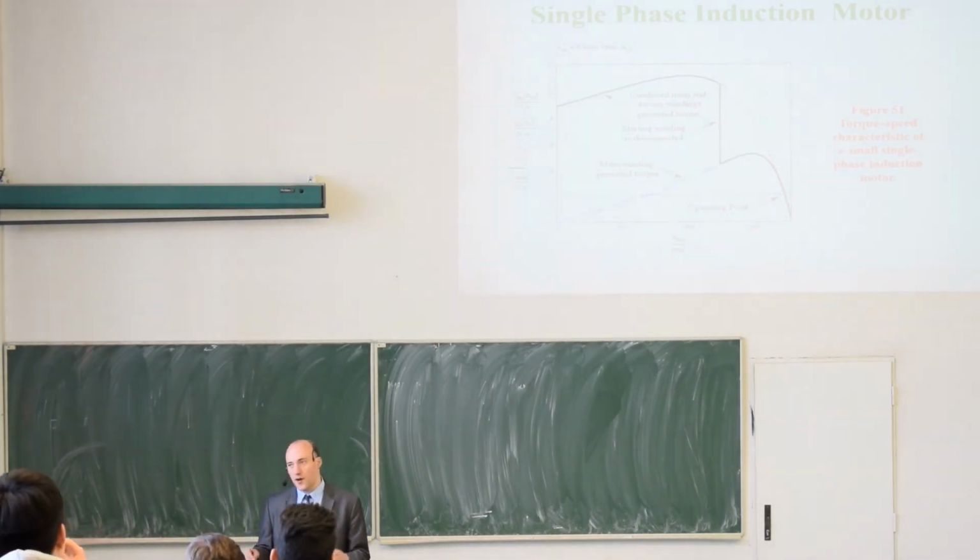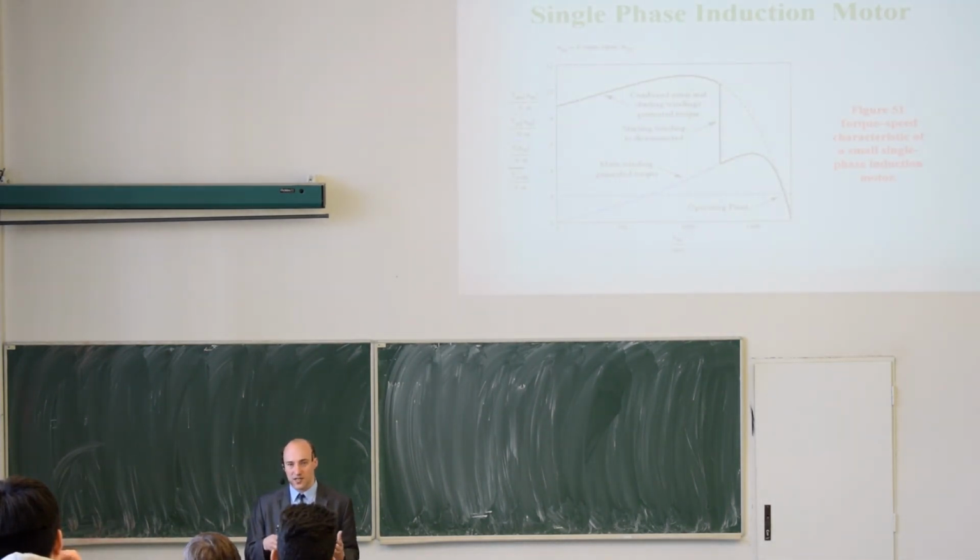So single-phase motors are not used for large applications. You will not find single-phase induction motors for 100 kilowatts, for example, because for this kind of power, the current going through the line would be very big. And since in the three-phase network, the current is much smaller, larger appliances are using three-phase power because the current is smaller and we can have thinner wires. And this means it's less expensive.